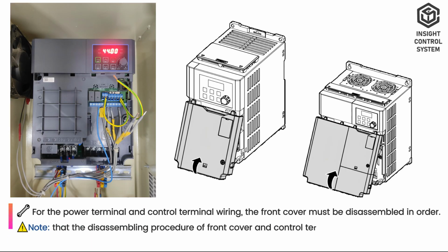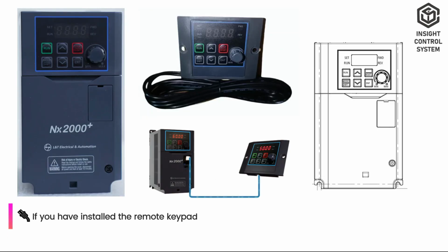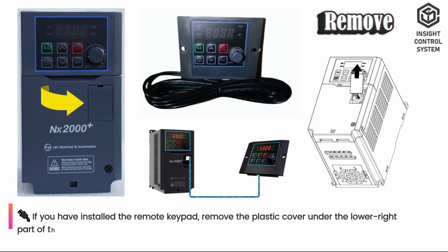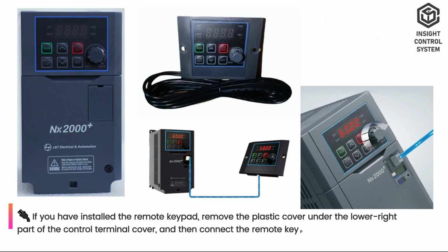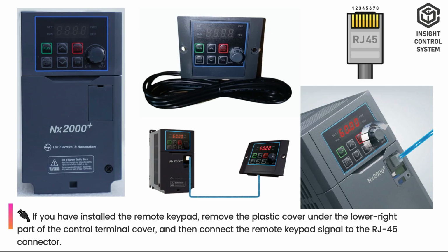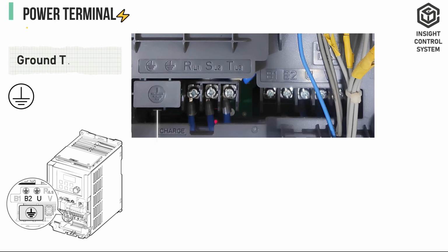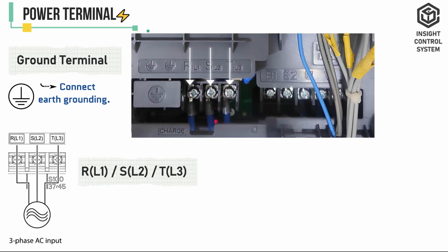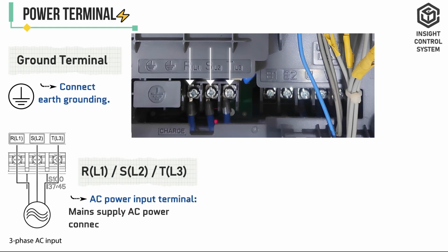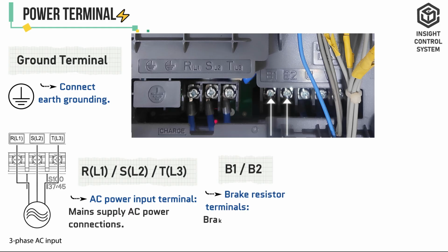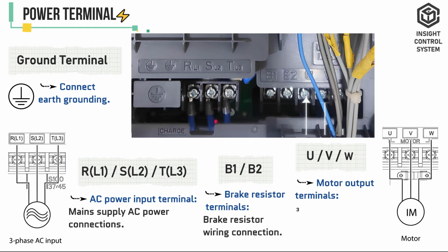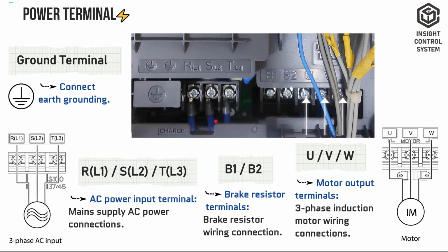Terminal connectors. For the power terminal and control terminal wiring, the front cover must be disassembled in order. If you have installed the remote keypad, remove the plastic cover under the lower right part of the control terminal cover, and then connect the remote keypad signal to the RJ45 connector. Power terminals. This is a ground terminal and connects to the earth grounding. L1, L2, and L3 are AC power input terminals connected to the mains supply. B1 and B2 are the brake resistor terminals. U, V, and W are motor output terminals used for three-phase induction motor wiring connections.